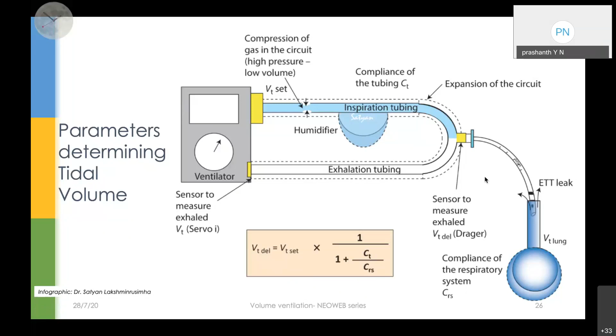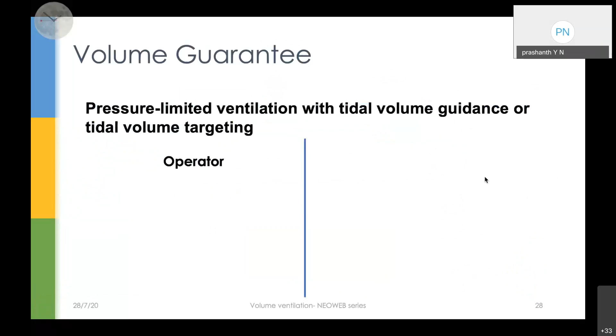Why? Going back to the previous slide, when we have these ET leaks and we look at flow measurements at the baby's end, it approximates the tidal volumes going into the baby's lung. The inspiration is not a good thing to look at, as the ET leak happens more in inspiration than in expiration. So the closest volume we can get is when we measure the flows at the baby's end. Second, when we look at expiration, the volume coming out of the lungs is what we need to look at.